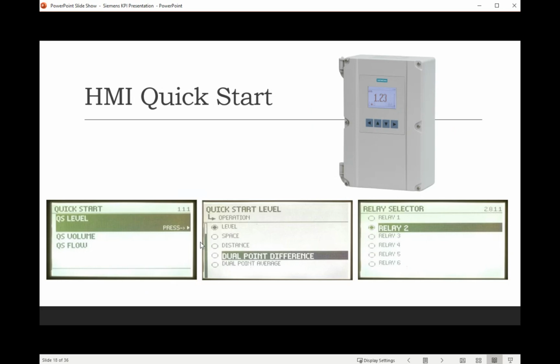Everything's parameter driven, but with the new HMI Hydroranger 200, everything is quick start driven. So you'd hit your right arrow to go into the menu structure, and then you have options for quick start. And then quick start level basically walks you through setting up an application for level. So instead of having to know what P001 is, it will tell you what's your operation, and I just select level. Very, very easy, especially when you're doing open channel flow. It walks you through open channel flow. You don't need to figure out what parameter it is. And then also setting up your relays with the new HMI is much easier compared to the other standard Hydroranger. So just something to consider.